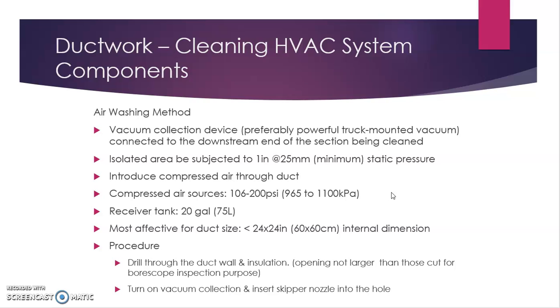So the first procedure, we have to drill through the duct wall and insulation. We have to make the opening not larger than the borescope inspection or our pressure pipe. We turn on the vacuum collection and insert the skipper into the hole. So one part will be vacuum and suck the air.